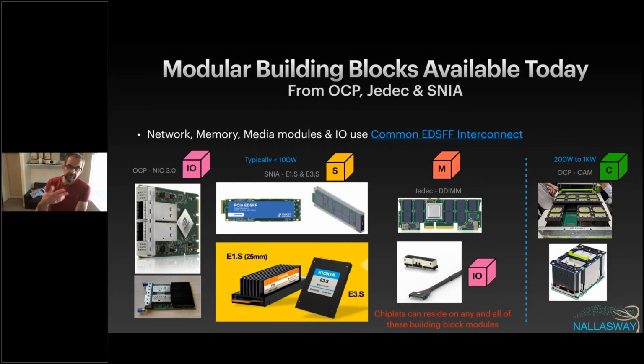This is a slide I updated slightly, but showed you the other day - we've got some wonderful building blocks in OCP, coming from OCP, JEDEC, and SNIA. This common EDSFF interconnect, I categorize into the less than 100 watt and 200 watts to a kilowatt with the OAM modules, the accelerator modules. You can see the cartoon blocks showing we've got all those building block pieces already there. I can buy an SSD in E1.S from Samsung, from Kioxia, Toshiba originally. We've got OCP NIC 3.0, I can get NIC cards with that connector. We've got JEDEC differential DIMMs, I can get differential DIMMs in that connector format.